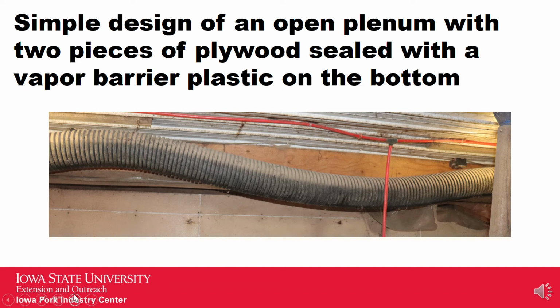As warm, moist air condenses the moisture on the plastic vapor barrier at the bottom of the plenum, the condensation is the energy transfer when you go from steam gas back to liquid, and it produces heat. Roughly 1,000 BTUs of heat energy is released when water as a gas phase changes to water as a liquid, per pound of water condensed. Heat is transferred from the warm air in the room to the colder air in the plenum, but that warm air is recycled back into the room through your preheat room, so no heat is lost.